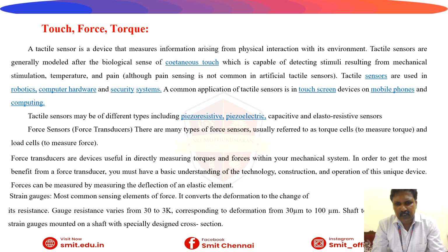Forces can be measured by measuring the deflection of an elastic element also. Strain gauges are the most common sensing elements of force. They convert the deformation into a change of resistance. The gauge resistance varies from 30 to 3K, corresponding to a deformation from 30 micrometer to 100 micrometer. The strain gauge is mounted on a shaft with a specially designed cross section.